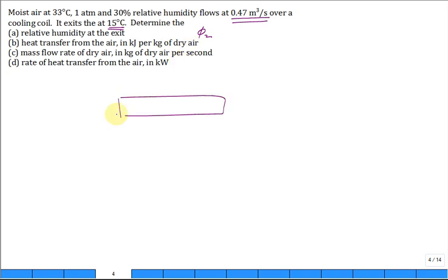So you have a little inlet, outlet, there's your coil, and it's a cooling coil, so you might want to put a drip pan in case there's some condensate. It flows in at state 1, out at state 2. You do a little energy balance around that coil, and there's a heat transfer out of the air because the water that's flowing through the cooling coil is getting warmer. So really cold water comes into the coil, warmer water leaves the coil, but the Q dot is out of the air. You do an energy balance.